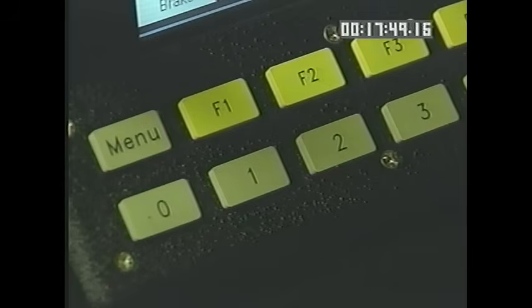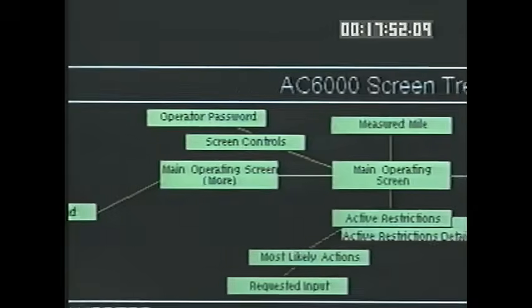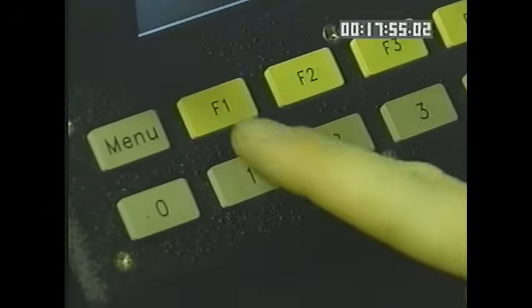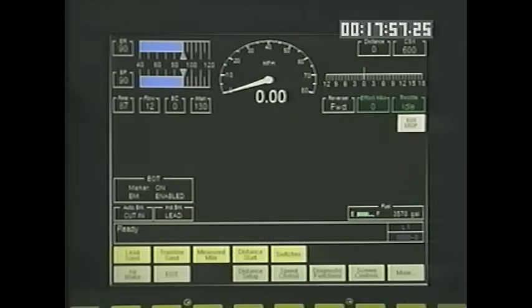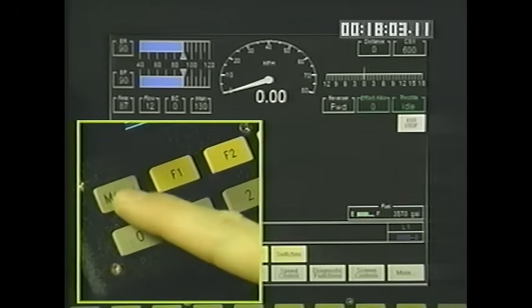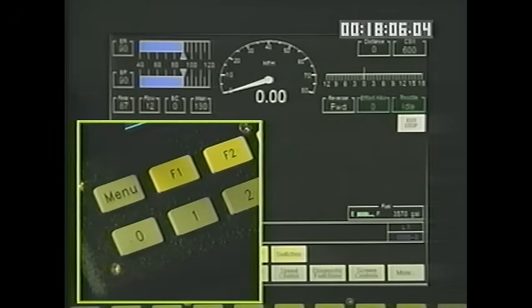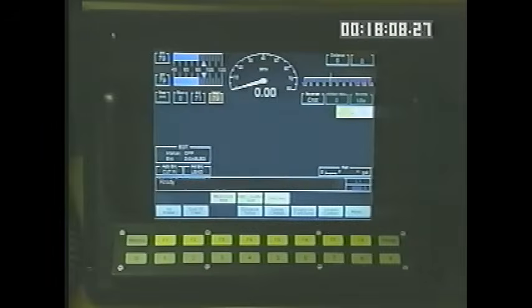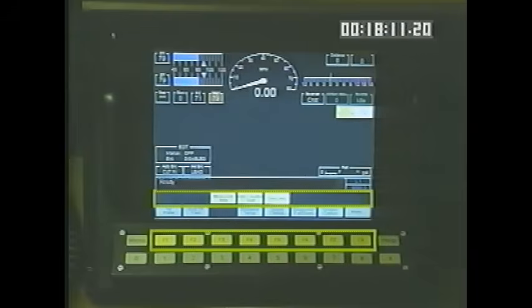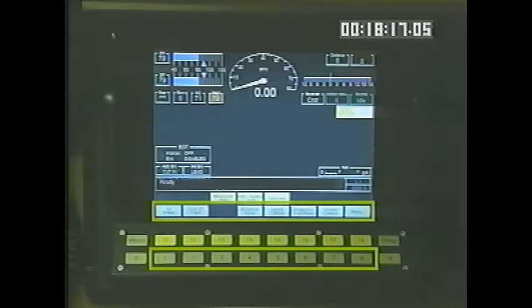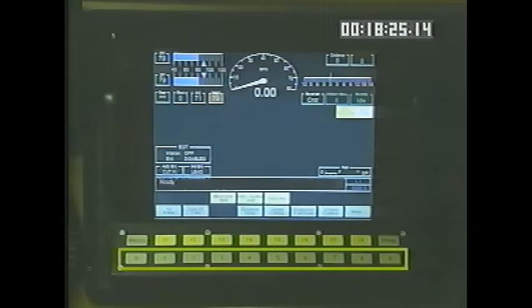Pressing the menu key on the top left-hand corner of the key rows displays the AC6000 menu screen. Press F1, the home key, to return the display to the main operating screen. Pressing the menu key twice on any screen brings up the gauge screen. The F1 through F8 keys correspond to the top row of choices on the screen menu. The 1 through 8 keys select the bottom row menu choices that are determined by the action being performed. The 0 through 9 keys are also used to input numbers.